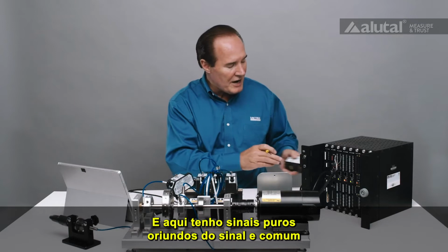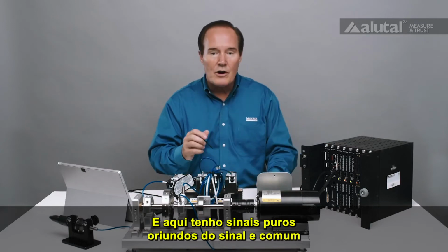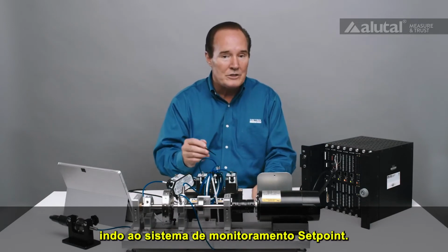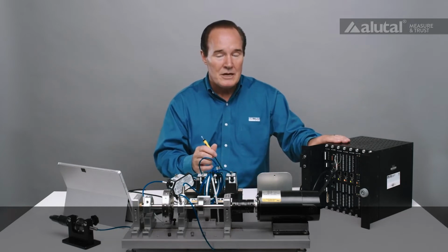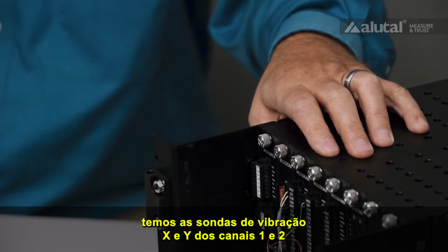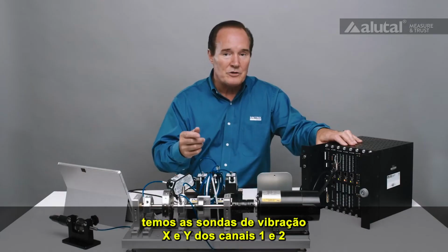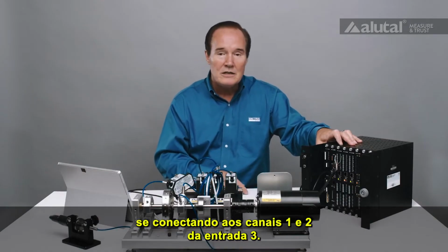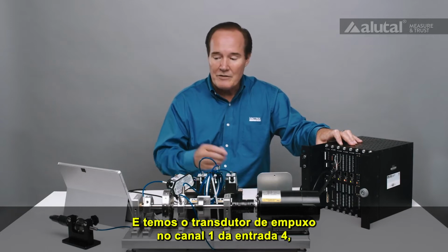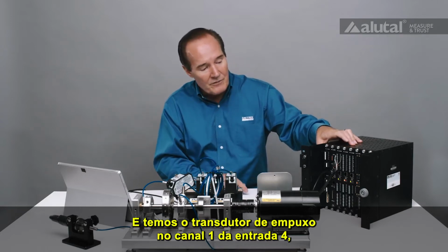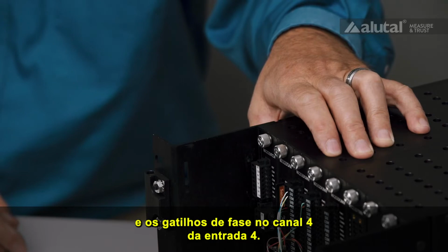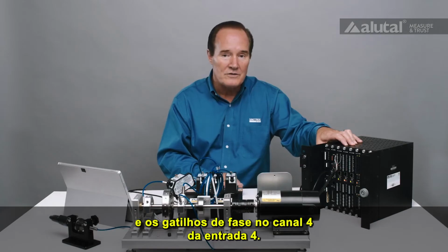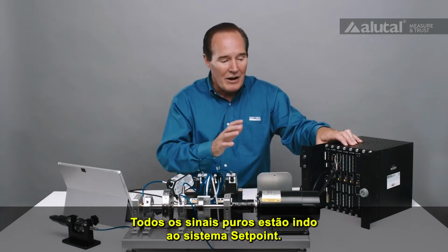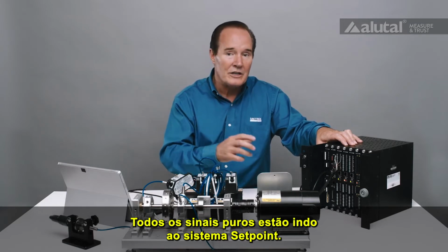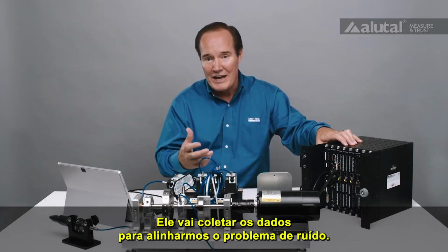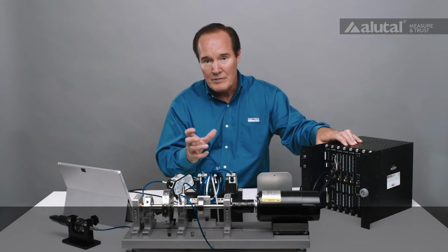And what I have is the raw signals from those signal and common going to the SetPoint monitoring system. On the SetPoint rack, we have the radial vibration probes X and Y, channels 1 and 2 going into slot 3, channels 1 and 2. And then we have the thrust transducer going into slot 4, channel 1, and the phase triggers on channel 4 of slot number 4. So we've got all the raw signals going into the SetPoint system, and that's going to gather our data so we can look at this noise problem.